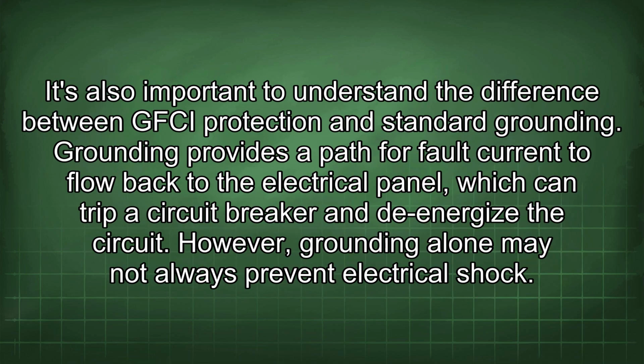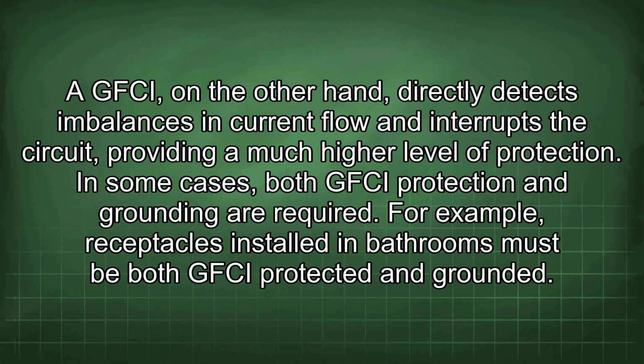It's also important to understand the difference between GFCI protection and standard grounding. Grounding provides a path for fault current to flow back to the electrical panel, which can trip a circuit breaker and de-energize the circuit. However, grounding alone may not always prevent electrical shock. A GFCI, on the other hand, directly detects imbalances in current flow and interrupts the circuit, providing a much higher level of protection. In some cases, both GFCI protection and grounding are required. For example, receptacles installed in bathrooms must be both GFCI protected and grounded.